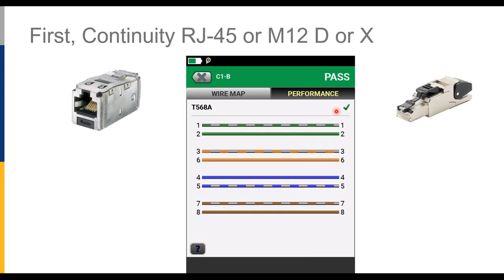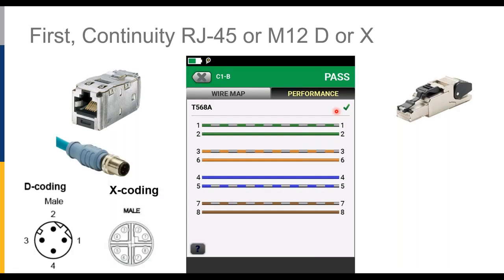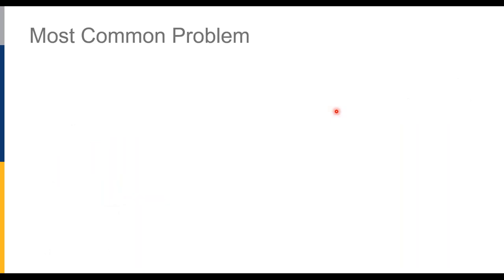We'll also see continuity with M12 connectors — round connectors more common in industrial environments because they're heavy-duty and won't shake loose, addressing the Mechanical, Ingress, and Climatic elements of MICE. You can screw them down so they won't come loose or be as susceptible to dirt or water. There are two flavors: the D-code, which has two pairs to run 10 and 100 megabit Ethernet, used for years; and the X-code — Roman numeral 10 — a four-pair version allowing use of Category 6A cable to run 10 gigabit communication.